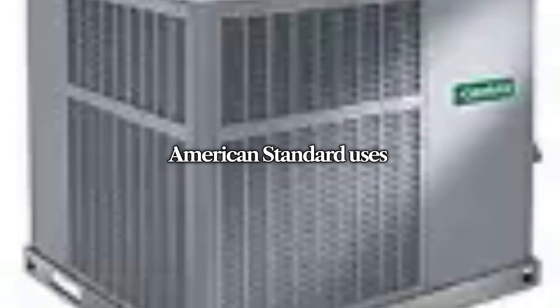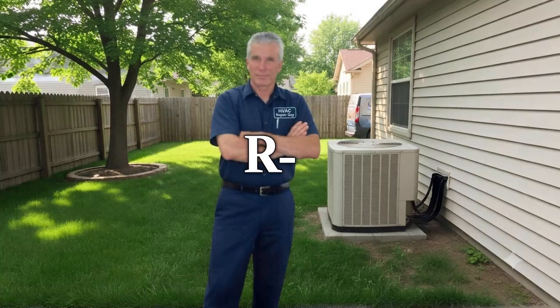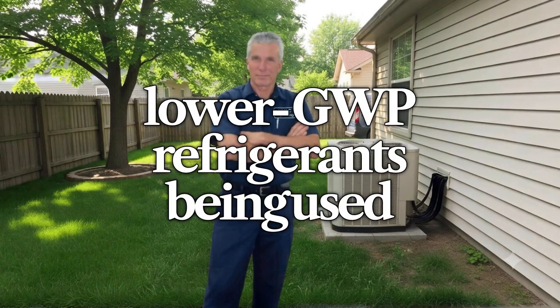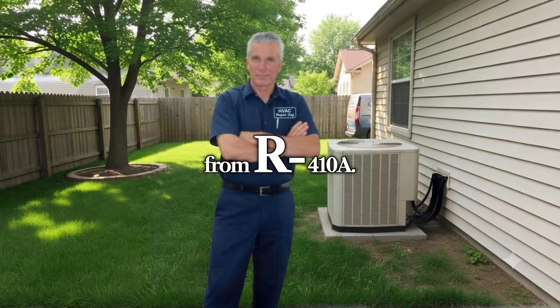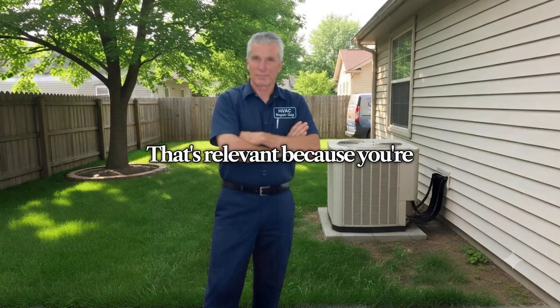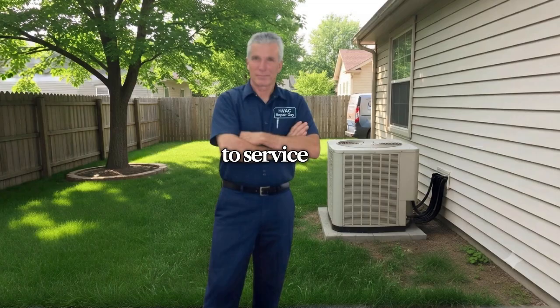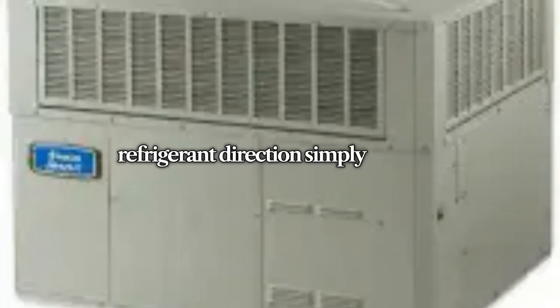The Century uses R410A refrigerant, while the American Standard uses R454B. R454B is one of the newer lower GWP refrigerants, being used as the industry moves away from R410A. That's relevant because you're buying equipment you're hopefully going to service for many years. The American Standard gets the nod from me on refrigerant direction simply because R454B is the newer platform.